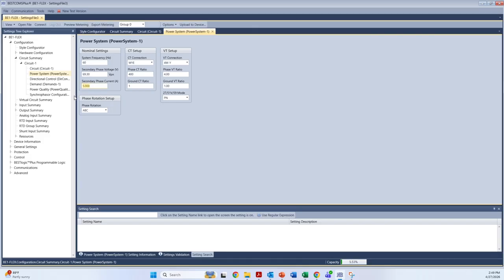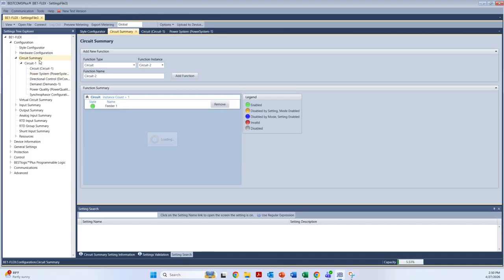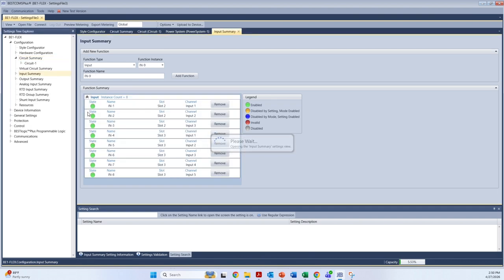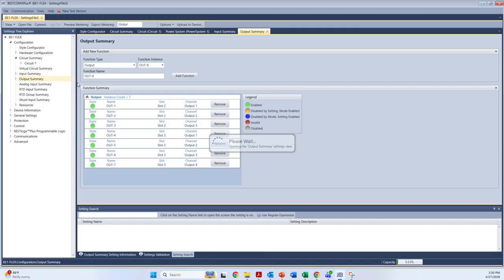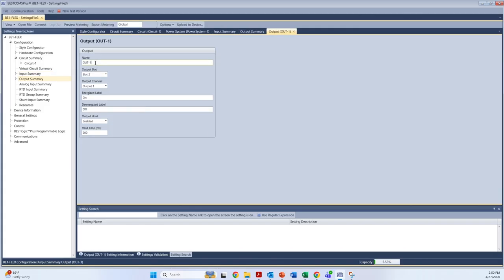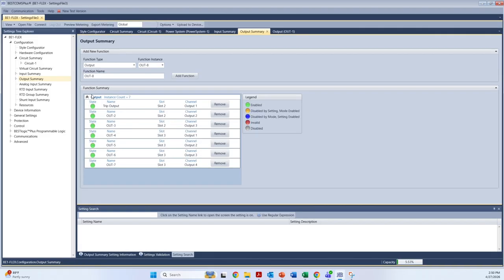60 hertz, 5 amp input is the default. 4-wire Y is the default. If you need to do 3-wire delta, you just use the drop down to change and make any changes. Everything else you can leave as default if you're not using the ground or the VT or CT. So that's a setup for the power system. Any inputs and outputs, notice it maps them out by slot 2, input 1, and goes down to input 8 total. And then the outputs, you can label, and it's mapped as well based on the slot and the output on that slot.